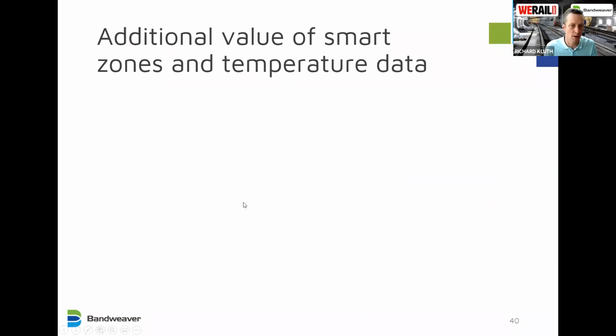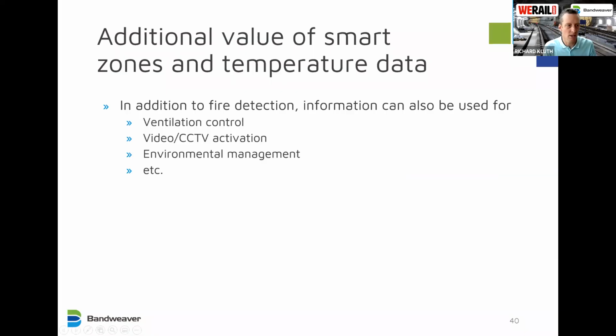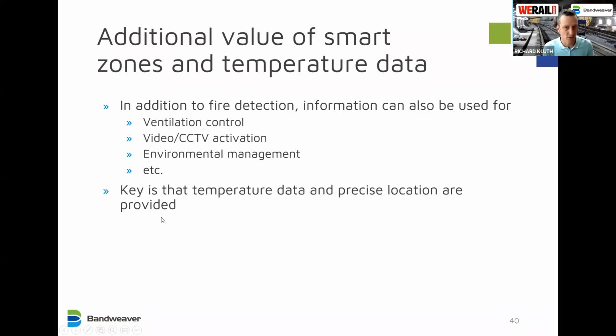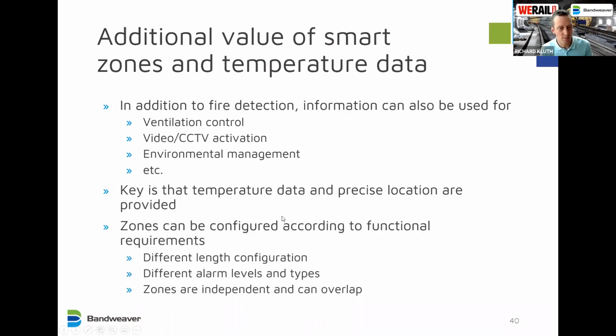So the final advantage we'll be talking about will be the smart zones, and how you use that temperature data. In addition to fire detection, the information can be used for ventilation control, to adjust the fan speed and when to turn them on or off, coordination of video CCTV feeds, for example, used in conjunction with evacuation or initial incident investigation, and environmental management if the tunnel has climate control issues. And the key to the smart zones, we're saying, is that you do get the accurate temperature data and the precise location. And then with the multiple different zone types, you can configure them according to functional requirements. And this can be different lengths, different alarms, and they're completely independent and can overlap.